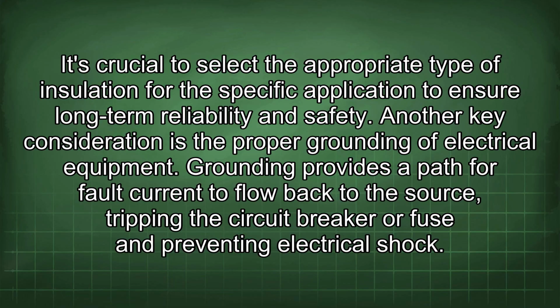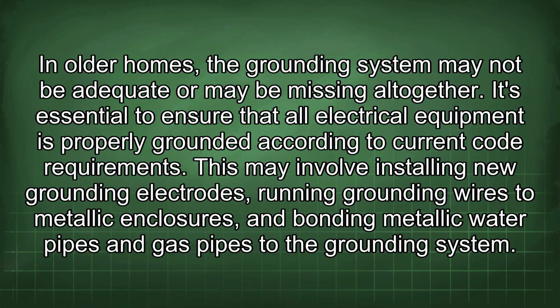Another key consideration is the proper grounding of electrical equipment. Grounding provides a path for fault current to flow back to the source, tripping the circuit breaker or fuse and preventing electrical shock. In older homes, the grounding system may not be adequate or may be missing altogether. It's essential to ensure that all electrical equipment is properly grounded according to current code requirements. This may involve installing new grounding electrodes, running grounding wires to metallic enclosures, and bonding metallic water pipes and gas pipes to the grounding system.